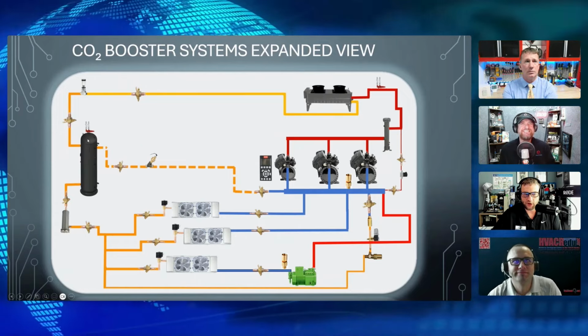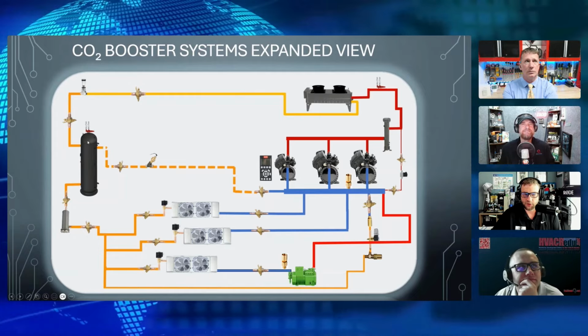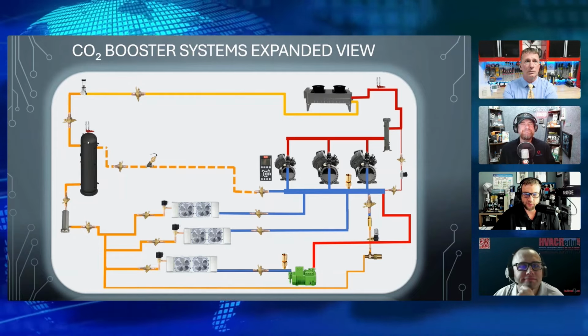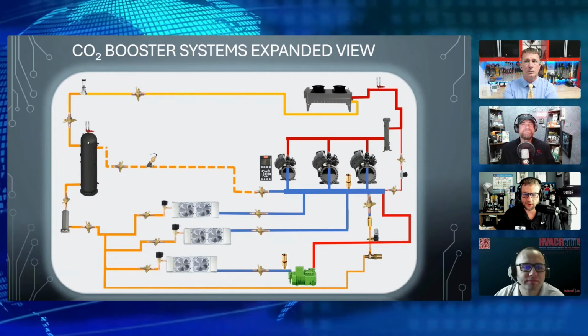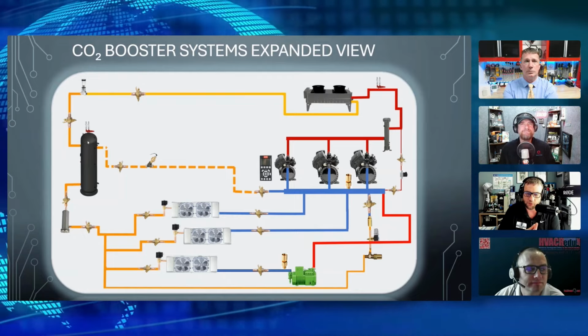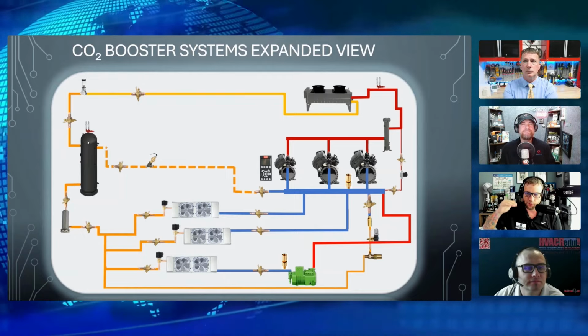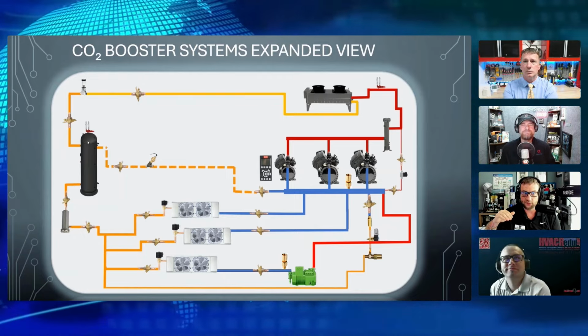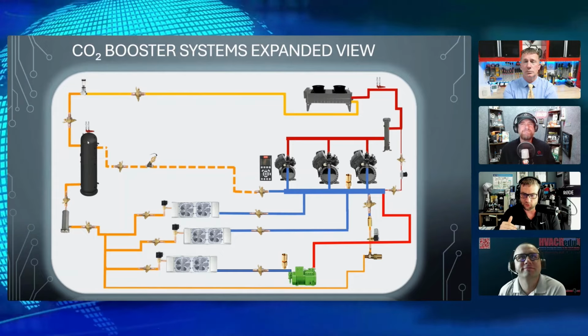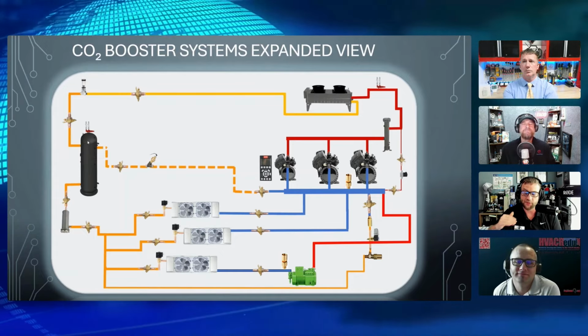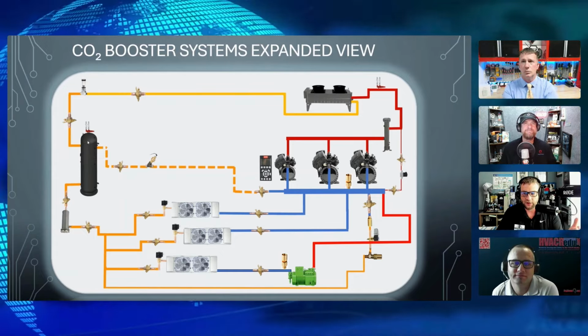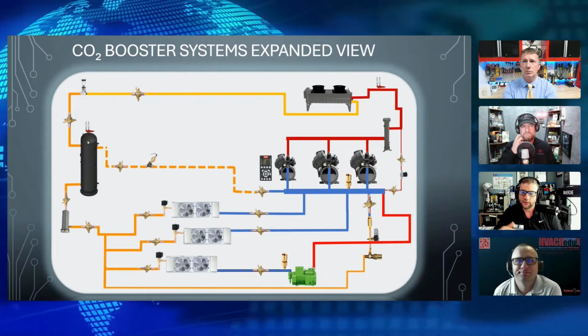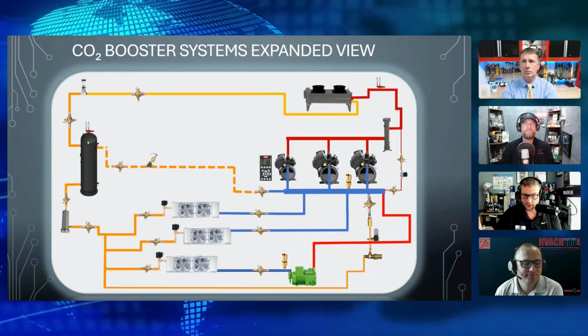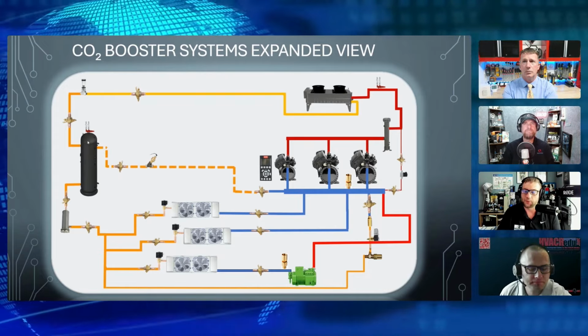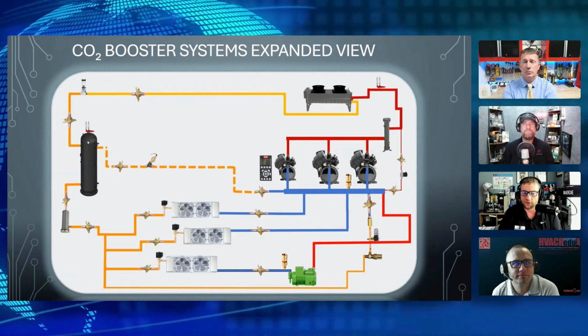Because when you lower the pressure coming out of the HPV, you could have potentially, let's just say, 1400 pounds. We have to reduce the pressure in order to get it to something we can control underneath that critical point. So we drop that pressure from approximately 536 PSI to 490 PSI. Well, how do we do that? If we're dumping X amount of pressure in there, how do we mitigate that down?